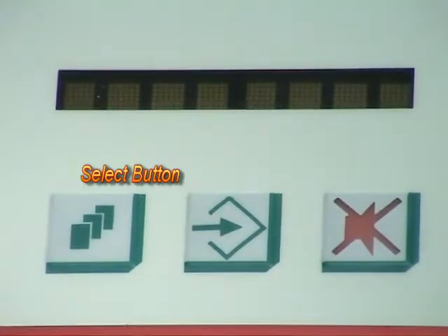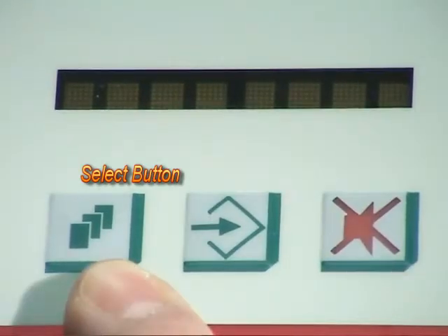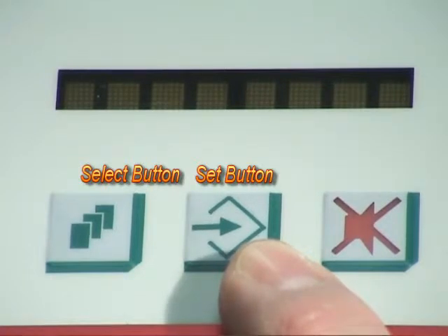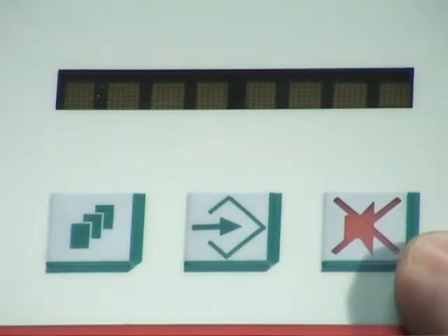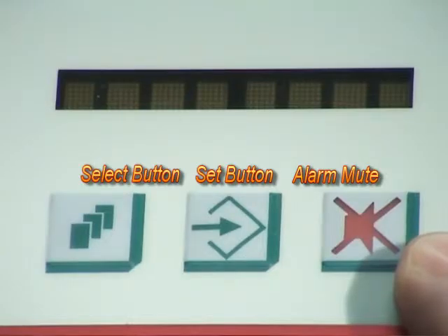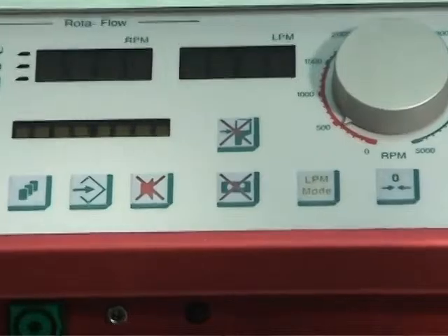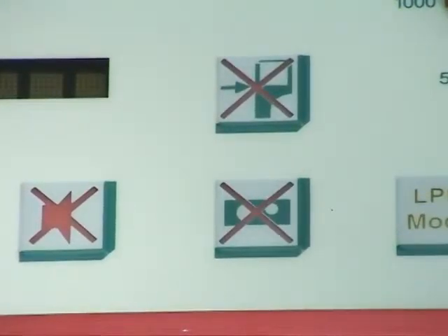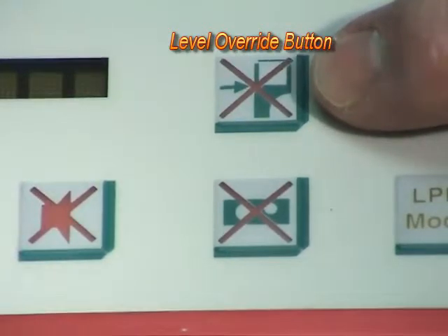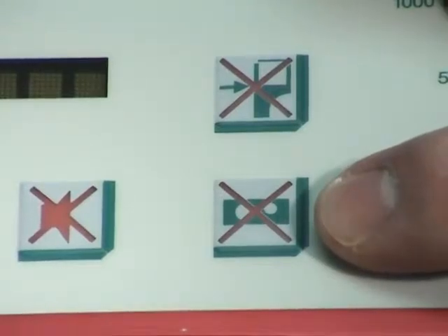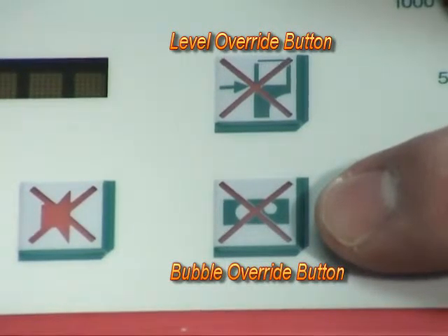The Select button allows you to select menu options. The Set button allows you to select items in the submenu and set the mode. The Alarm Mute button is an audible alarm mute which flashes with each new alarm condition. The Level Override button, you press for 3 seconds to override the level alarm, which makes it flash. A single press reactivates the level alarm. The Bubble Override button, again, you press for 3 seconds to override the bubble alarm, and a single press reactivates the alarm after being overridden.